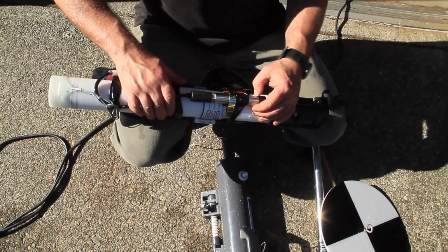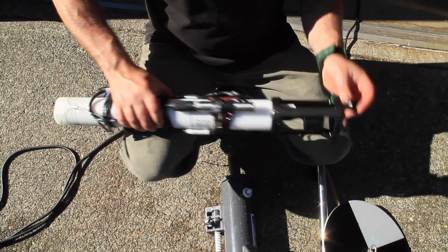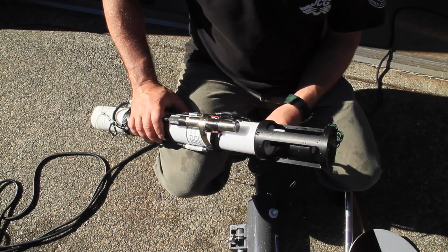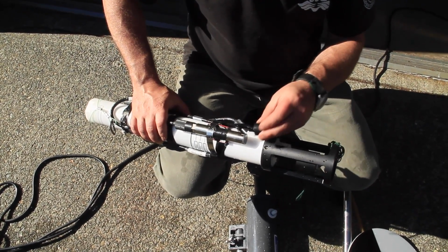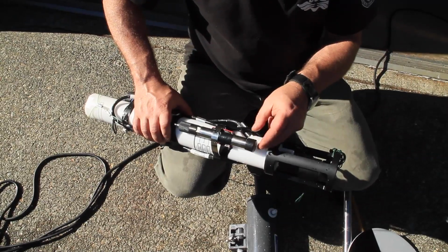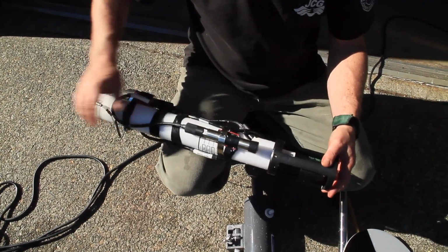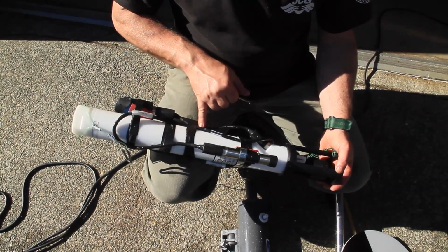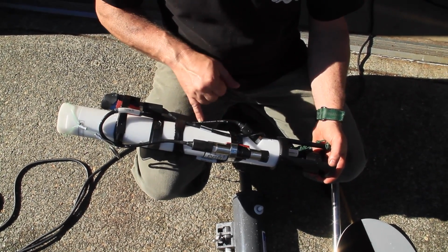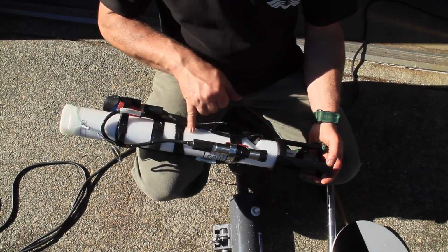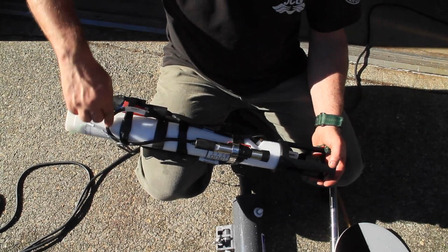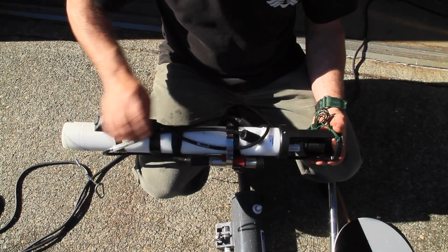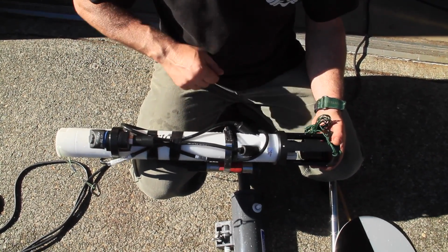The fluorometer has a dust cap on it. And you want to make sure that the face of the sensor is clean, and you try not to scratch it, and this cap just goes on to keep it from being bleached by sunlight, so you don't want to bleach it in broad daylight. All the cables, you want to make sure that they look like they haven't had any damage to them, that they're attached to the CTD, that there are nice lazy bends in them, and that they're not chafing on any of the hose clamps or anything else. Watch the end of the hose clamp there, that it doesn't catch on anything.